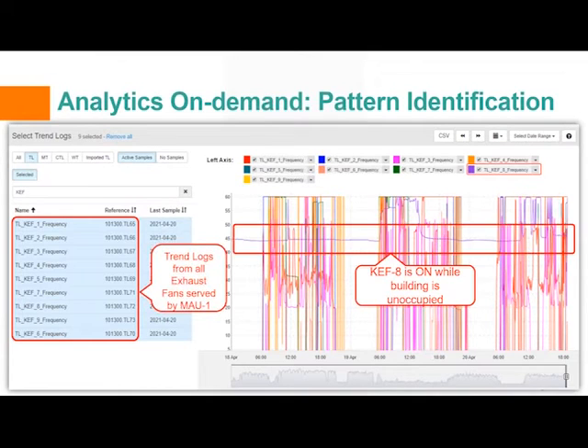The trend log view on the right shows all of the selected exhaust fans served by MAU1 and how their individual frequency values fluctuate. You'll notice, however, that for some reason, KEF8, which is shown in purple, has remained on while the building was unoccupied. Knowing that the makeup air unit is interlocked with the kitchen exhaust fans, we've now identified the reason why the fans were running continuously during this period of time.